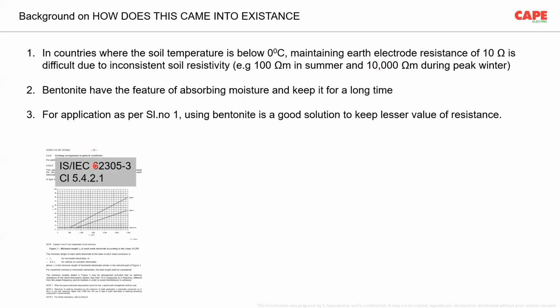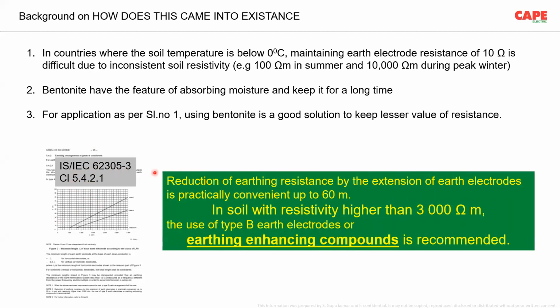As a result, the only place in a standard where this material is recommended is IEC 62305, clause 5.4.2.1. What is written is: reduction of earthing resistance by the extension of earth electrode is practically convenient up to 60 meters. That means if you want a long earth electrode, you can do it up to 60 meters. Now the second line is: in soil with resistivity higher than 3000 ohm meter, the use of type B earth electrode or earth enhancing compound is recommended.